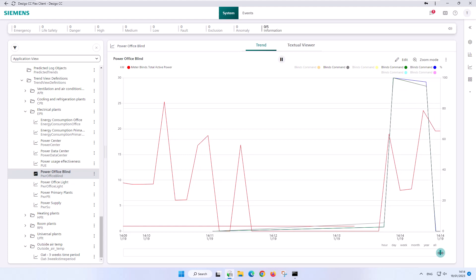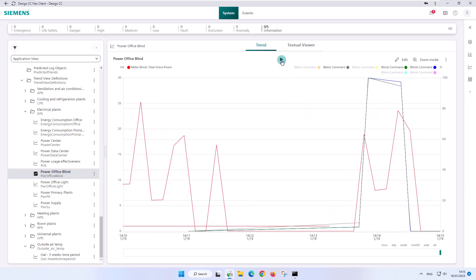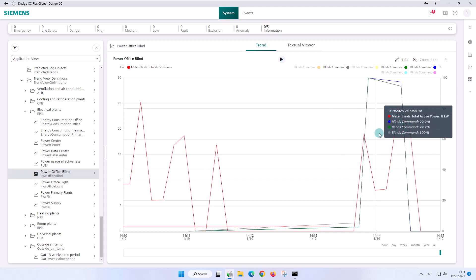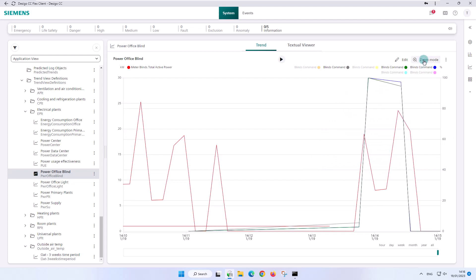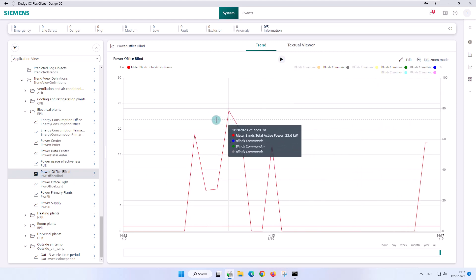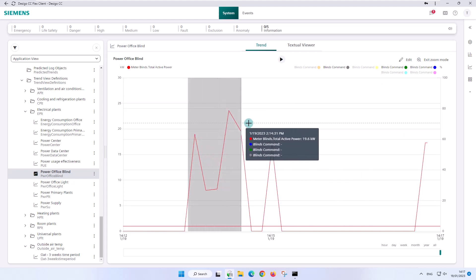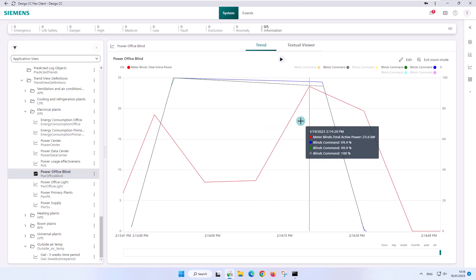We would like to find out when exactly and how high a specific peak value was. It is recommended to stop the update, which is done by clicking on this icon. We can now analyze this undisturbed without fearing that the trend view will change with a value update and that we will lose focus. The flex client offers another possibility to adjust the time range to the desired requirements: the zoom mode. We click on zoom mode and the mouse cursor changes into a cross that allows us to precisely define the time range in the chart itself. This function allows us to zoom into a very precise time period and reach our goal efficiently.